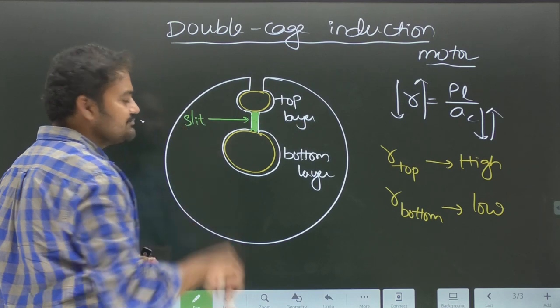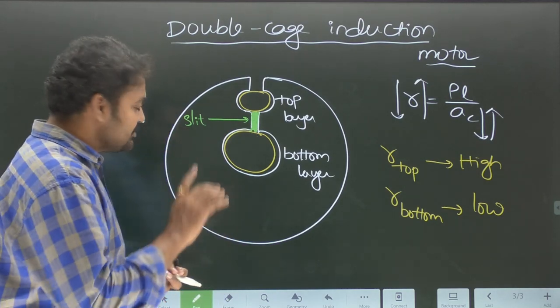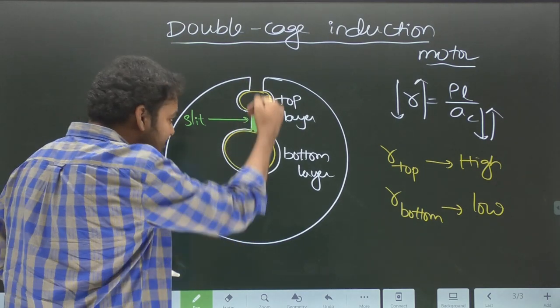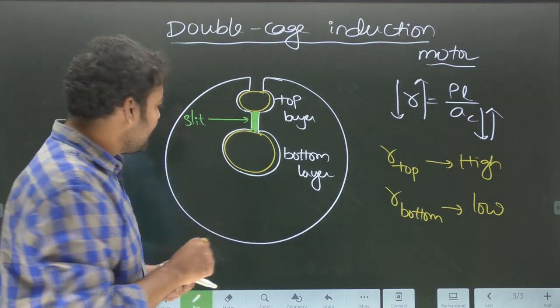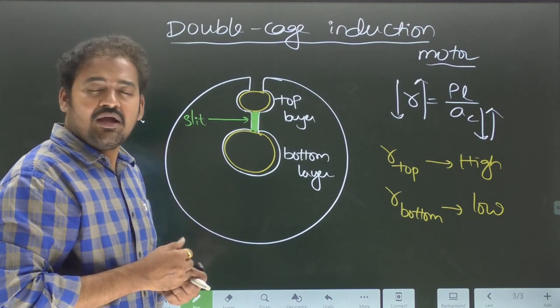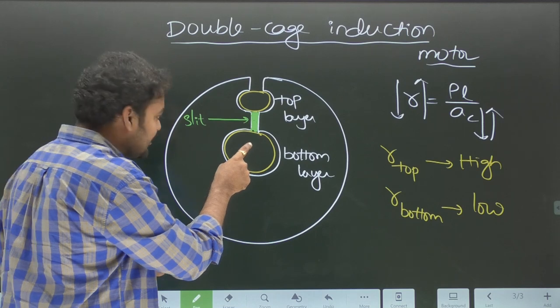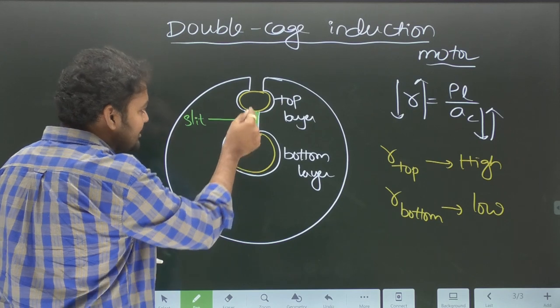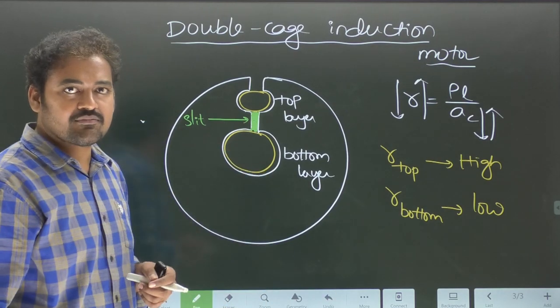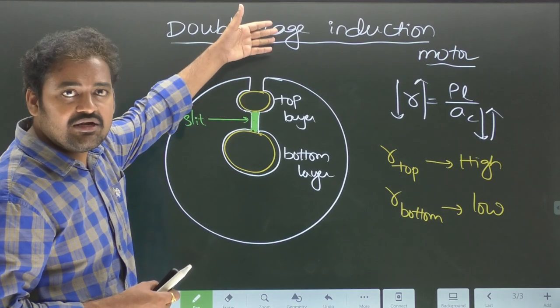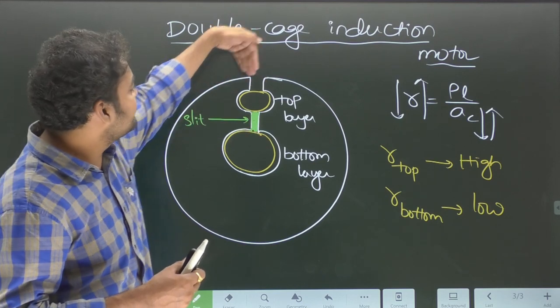The bottom layer is deep inside the rotor. When it carries current, copper losses generate heat in the bottom layer. That heat must be dissipated; otherwise the machine will overheat and get damaged. The slit helps transfer heat from the bottom layer to the top layer, and from the top layer that heat goes to the air gap medium, since air is the medium through which heat dissipates. For the top layer, being very near to the air gap, heat automatically dissipates.